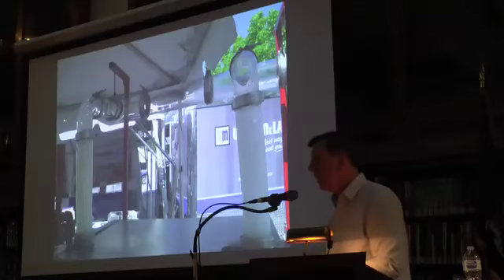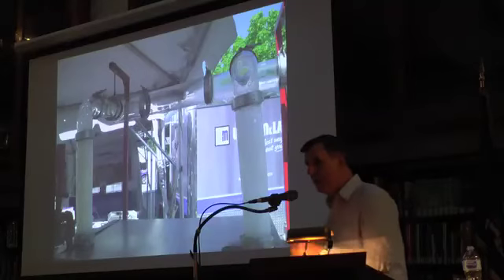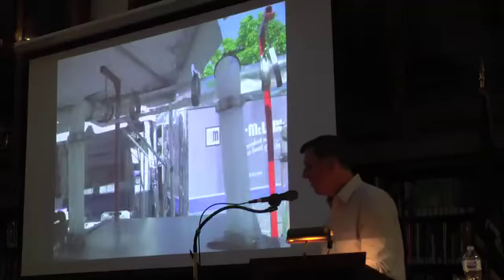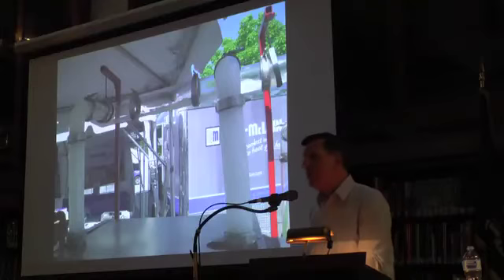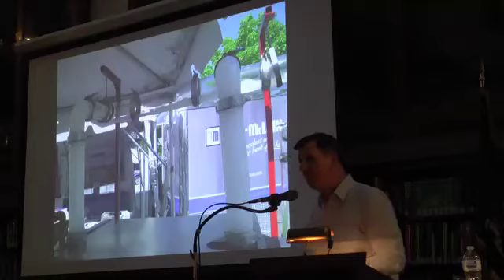That's normal. That's why you need at least 2 feet of height from the top of the boiler to where that header is, because this is what's going to happen in a modern steam boiler. And then it cascades over the top. Now, both of those risers are completely filled with water. If your header was lower than 2 feet, you don't have a steam boiler, you have a hot water boiler on a steam system. That's why you can't heat the building. And it tells you all this in the instructions.